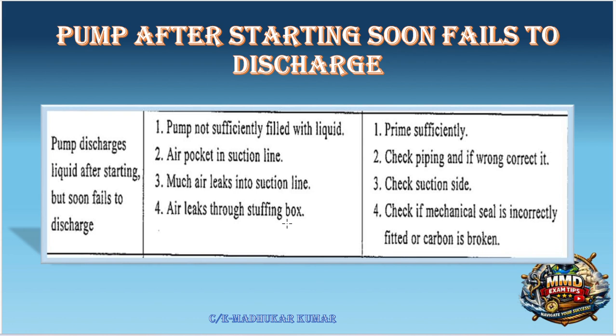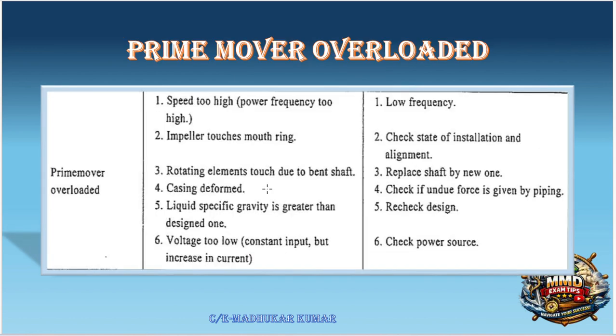Yes, the stuffing box gland leakage. If the mechanical seal is incorrectly fitted, carbon is broken or something like that, or if the gland packings and all are there, make sure that it is properly tightened, but it should not be over tightened also. So this also is one of the important parts. Prime mover overloaded, yes. Prime mover means the motor basically which is attached to the pump side. Okay. So speed is too high, power frequency too high. So then we have to go for the lower frequency. Basically, this is some electrical related part.